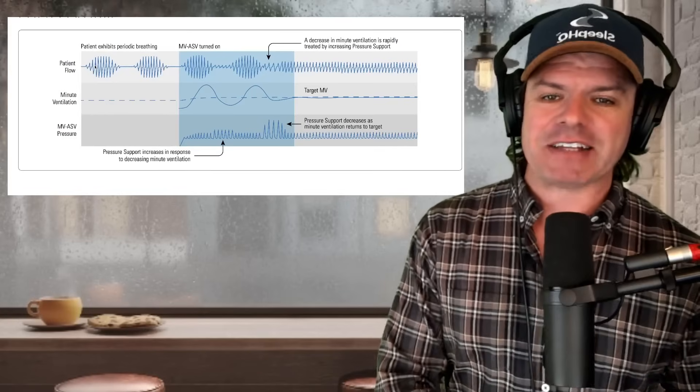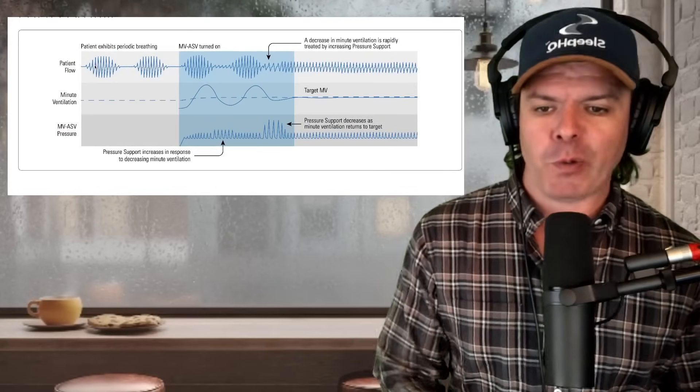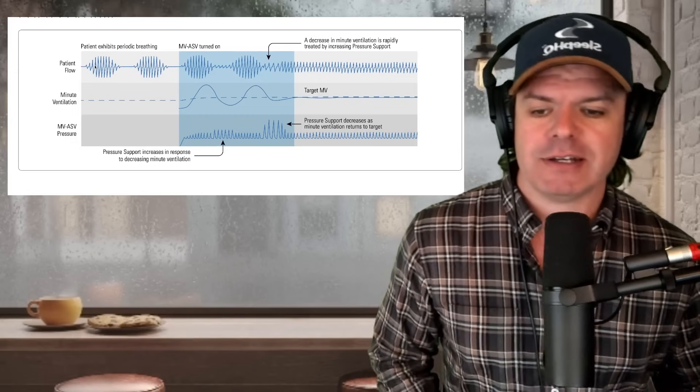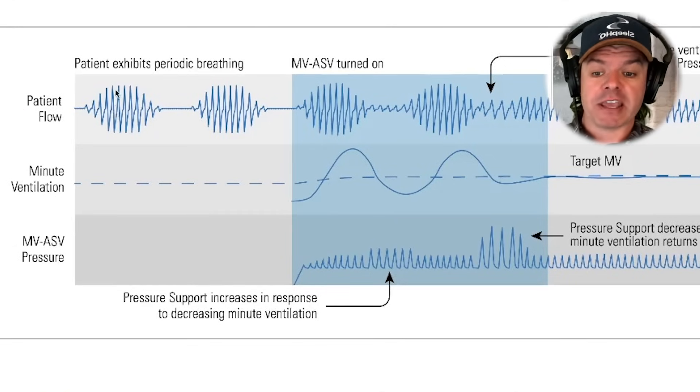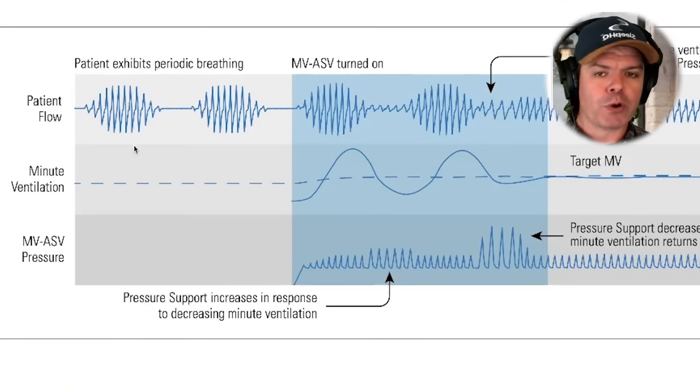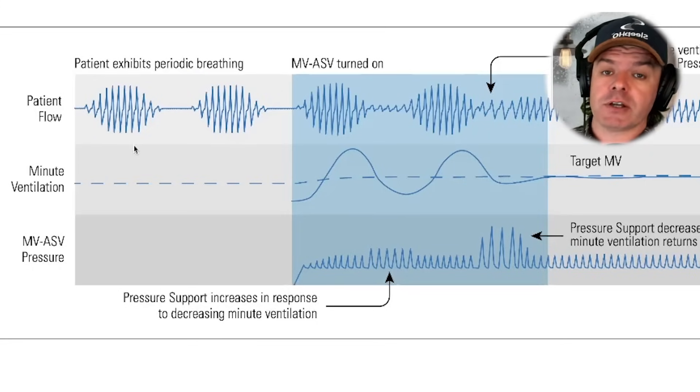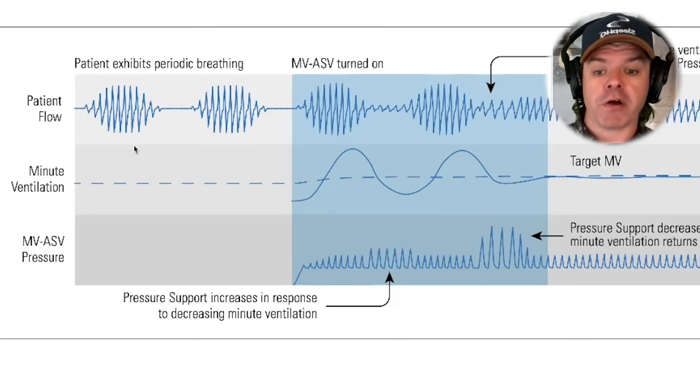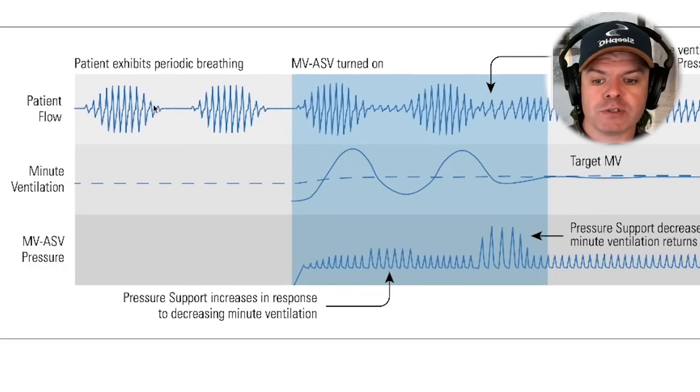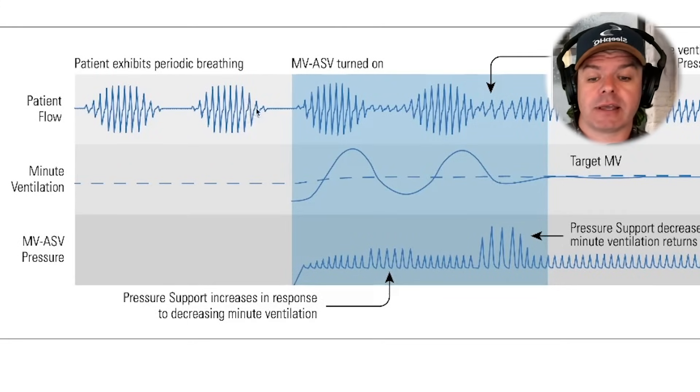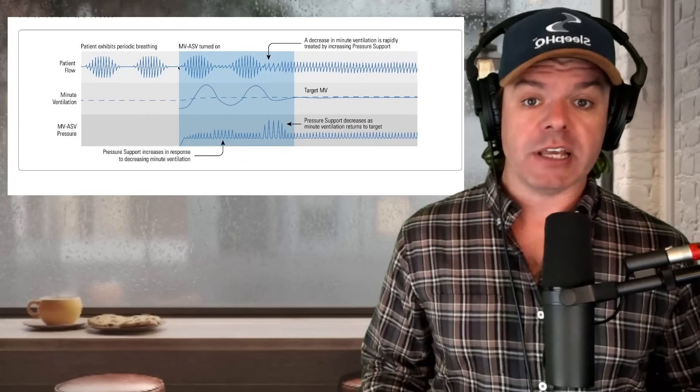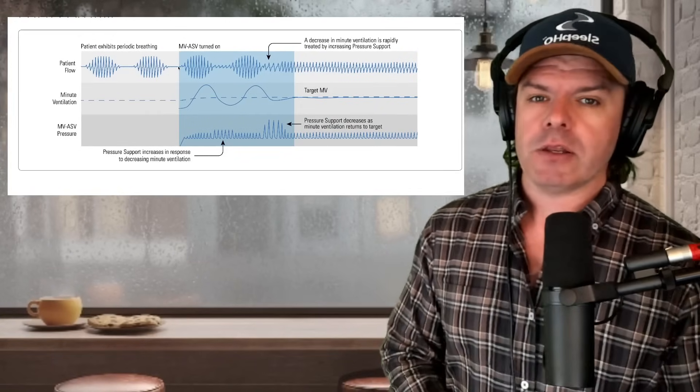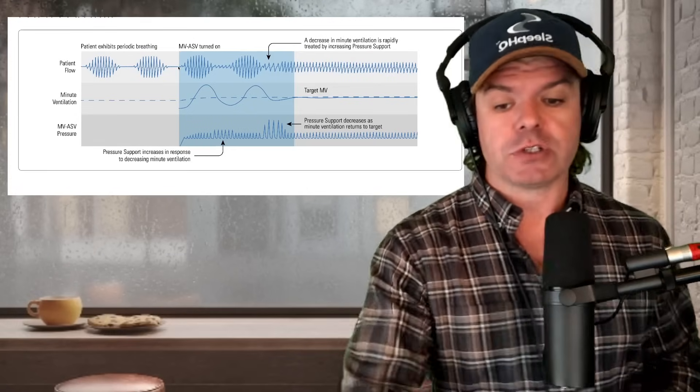Okay, so let me break it down for you. Now, ASV is some complex stuff, but just bear with me and I'll try my best. So this top trace here is the flow rate. Breathing in, breathing out, breathing in, breathing out. And you might recall this distinctive pattern. This is the Cheyne-Stokes respiration that we just looked at, this periodic breathing, where you have these breathing pauses between this waxing and waning pattern.